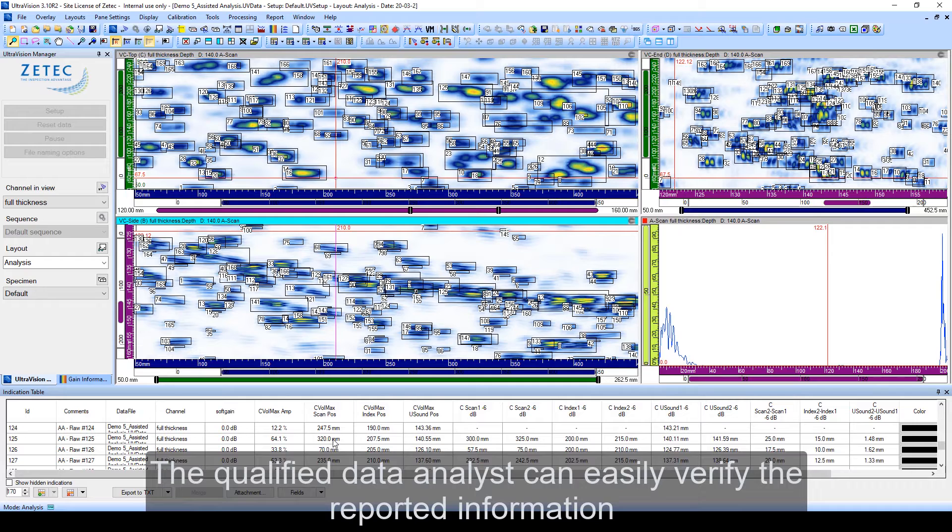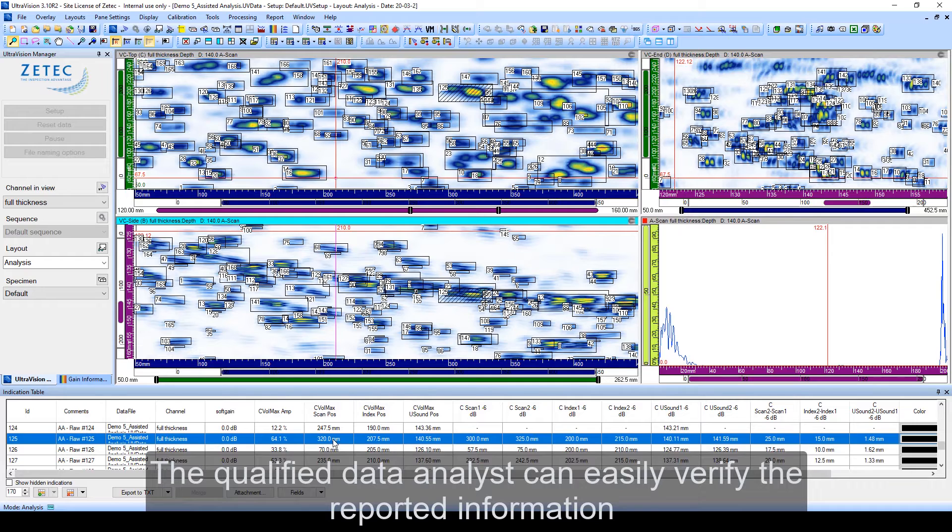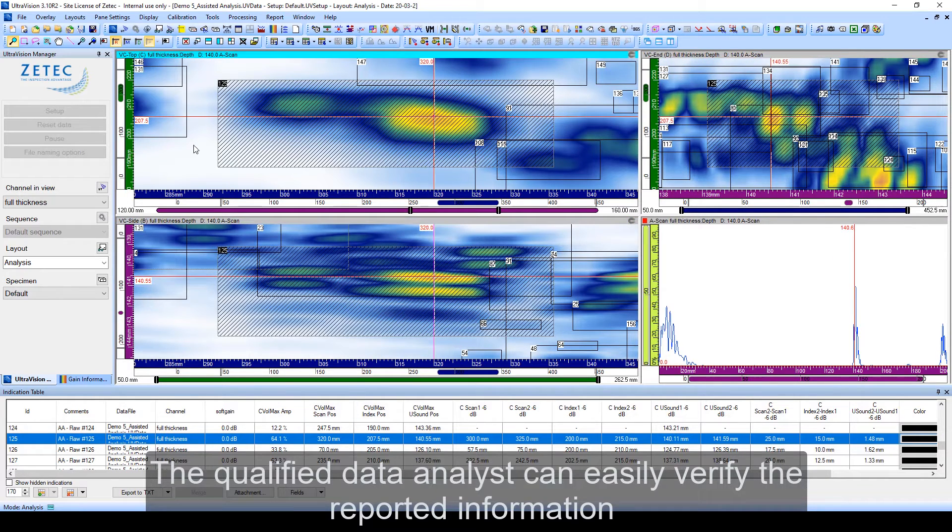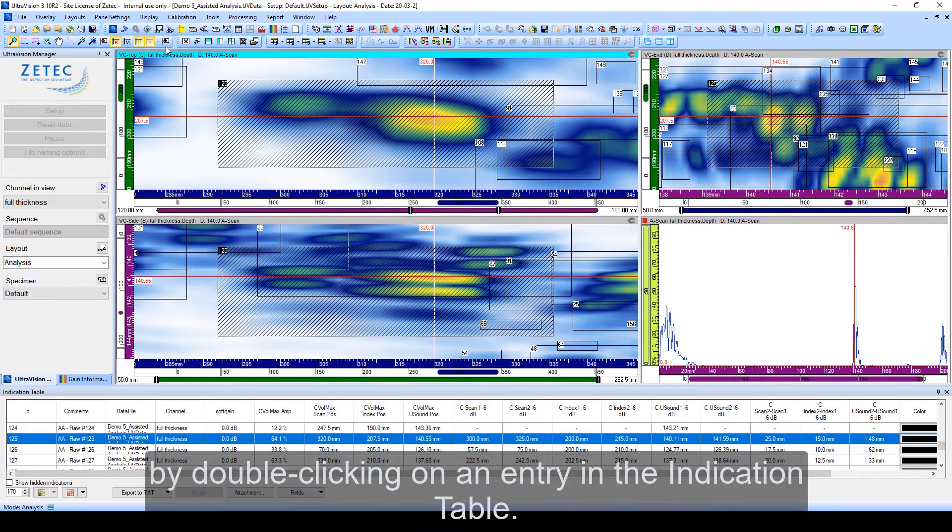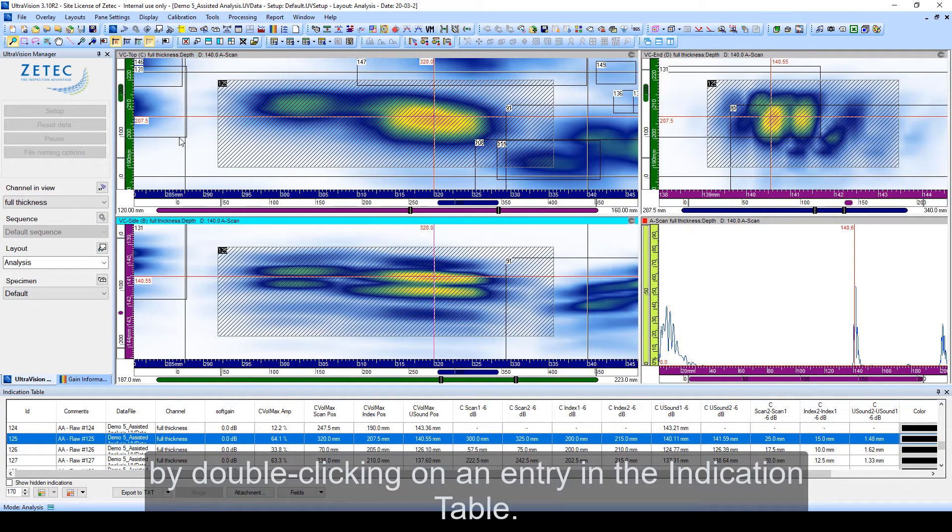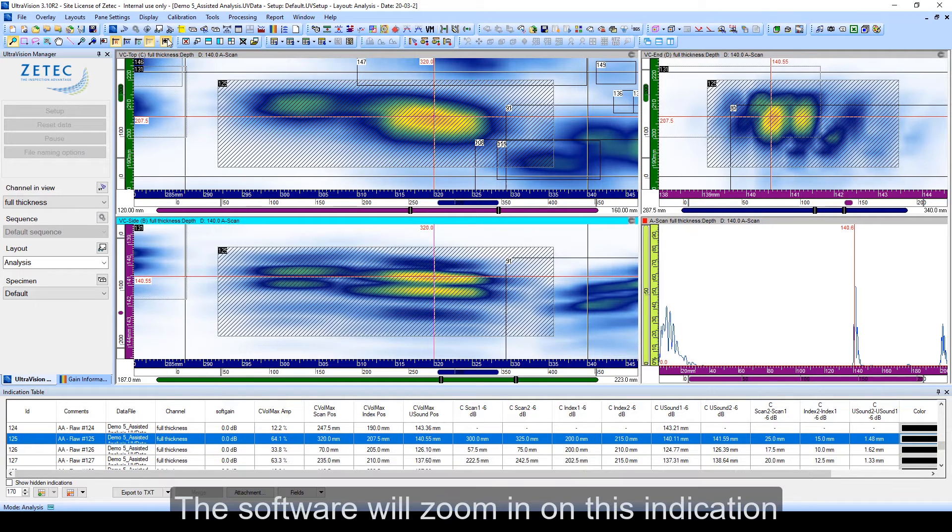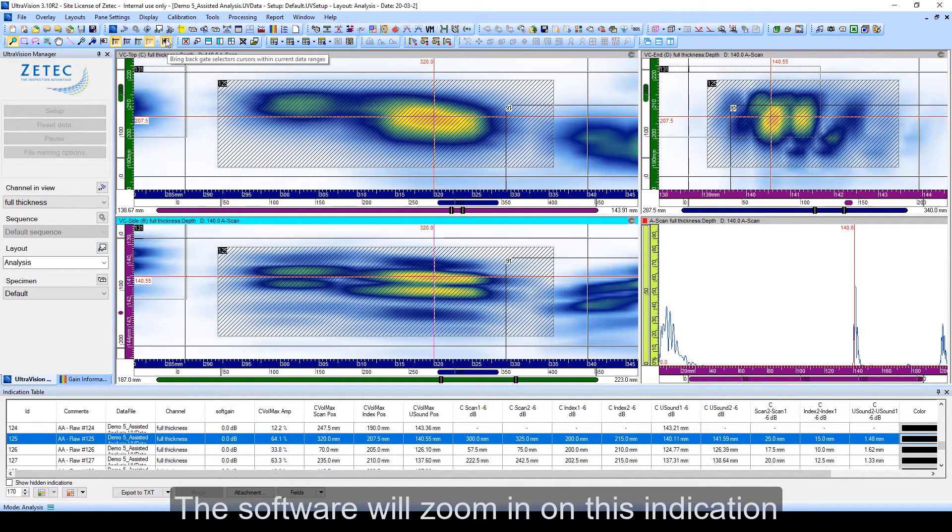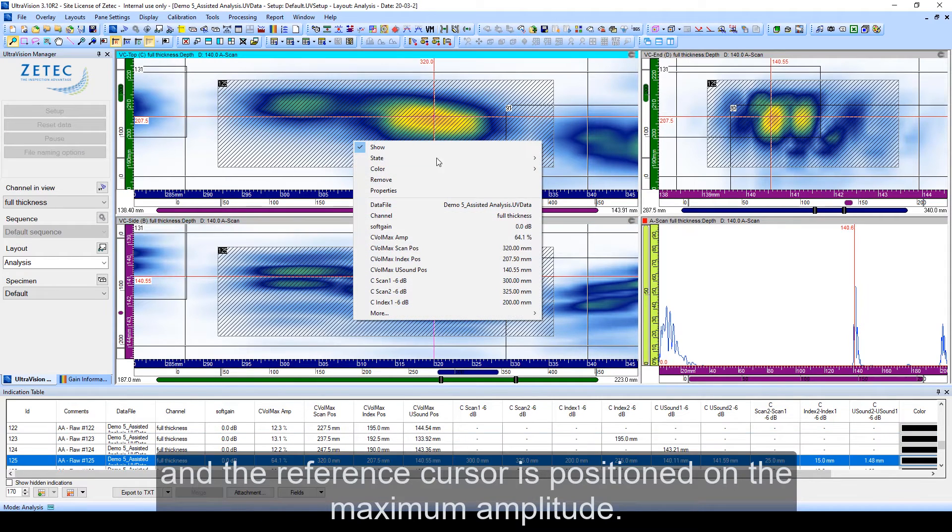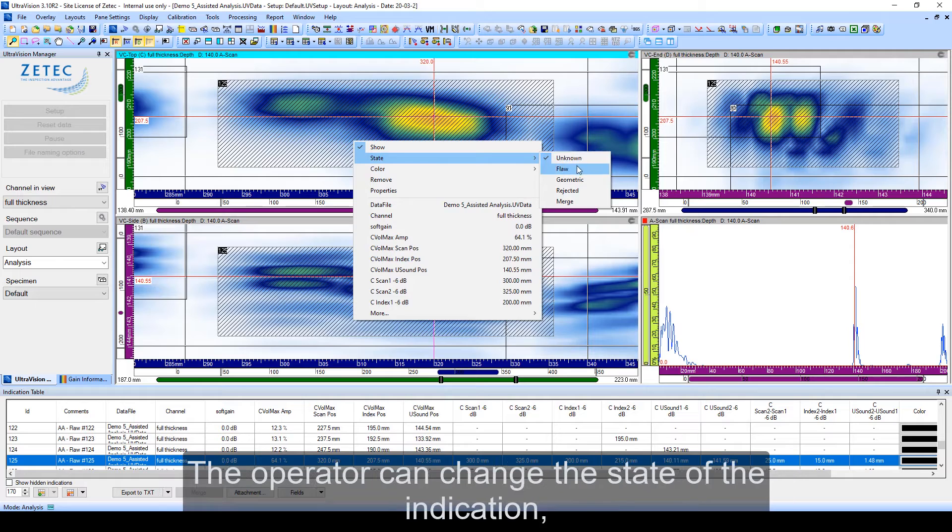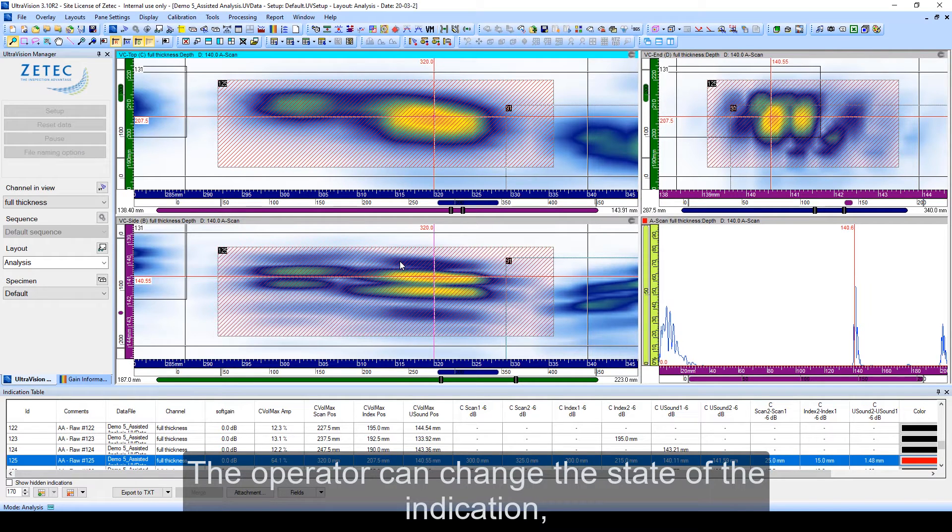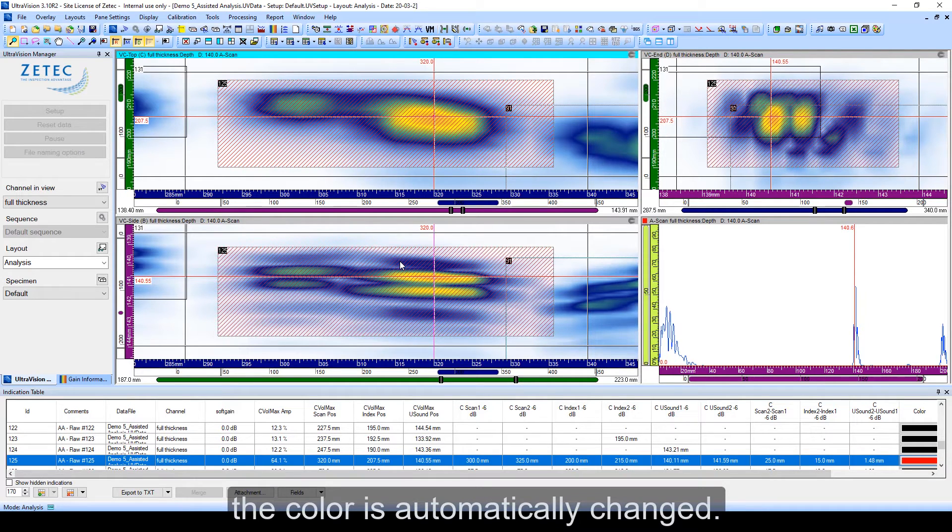The qualified data analyst can easily verify the reported information by double clicking on any entry in the indication table. The software will zoom in on this indication and the reference cursor is positioned on the maximum amplitude. The operator can change the state of the indication, and the color is automatically changed.